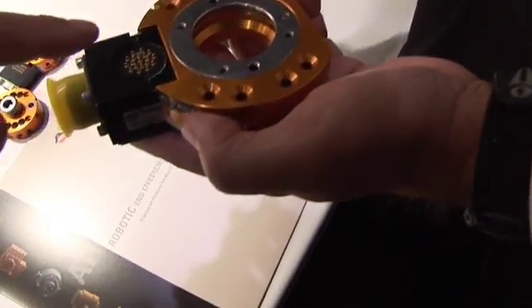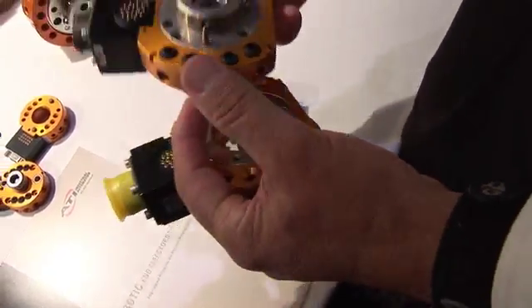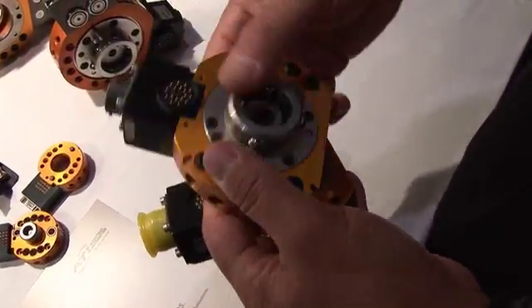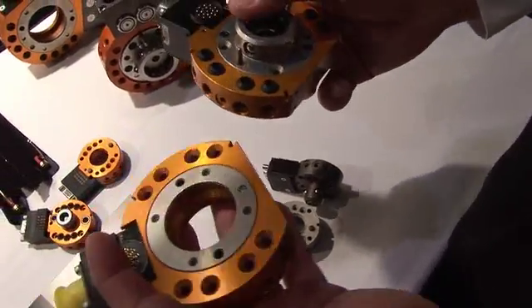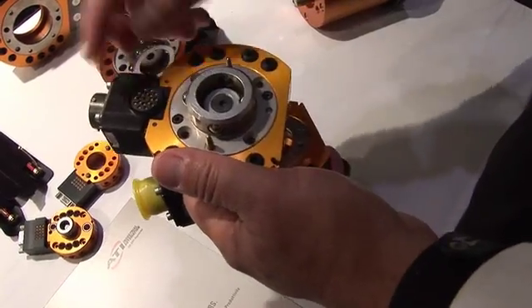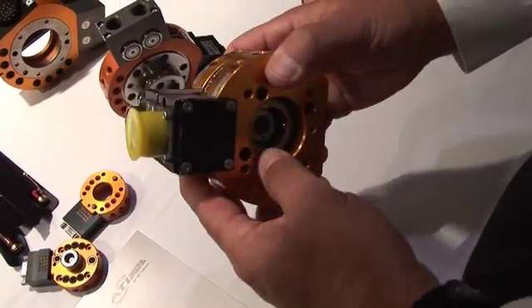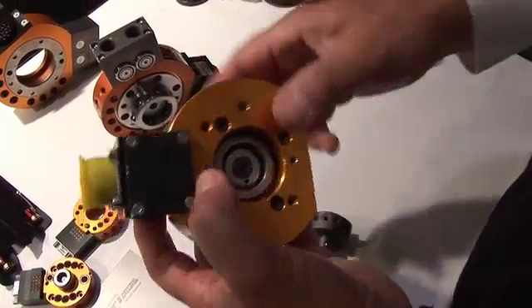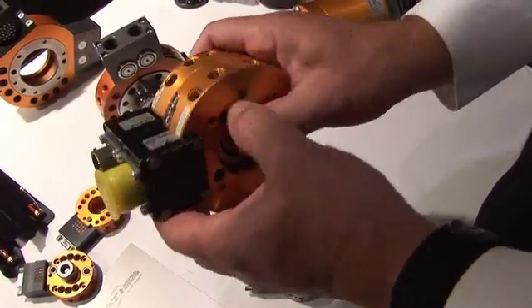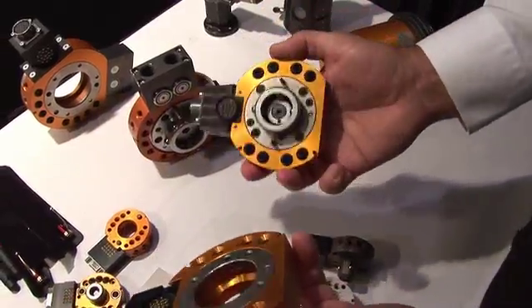Yes, we have robotic tool changers. You can reconnect electricity — I can see that here. Pneumatic power as well. Robotic tool changers allow you to use multiple tools in a robot cell. Here you have pneumatic pass-throughs as well as your electrical pass-through, so that when these couple, the robot will be able to pass all the utilities to the tooling through the tool changer. So that you can have multiple tools — with one robot you can do multiple jobs, multiple tasks.